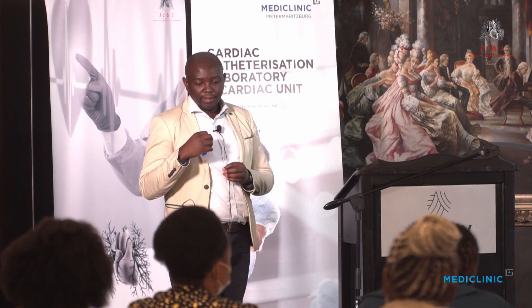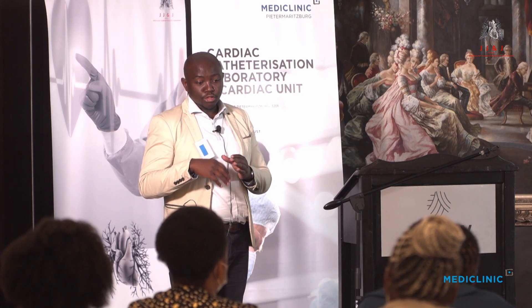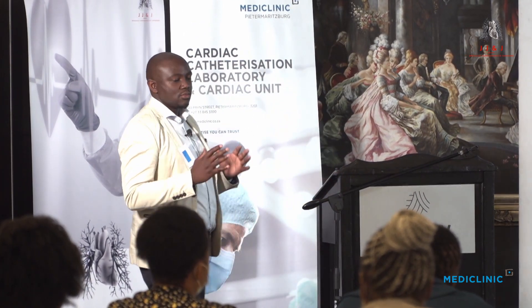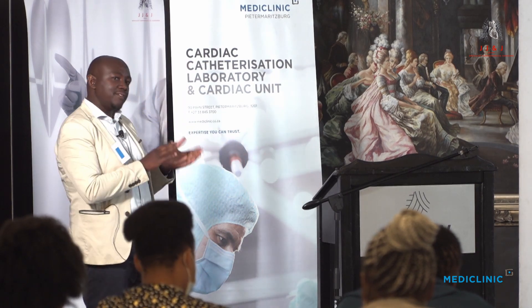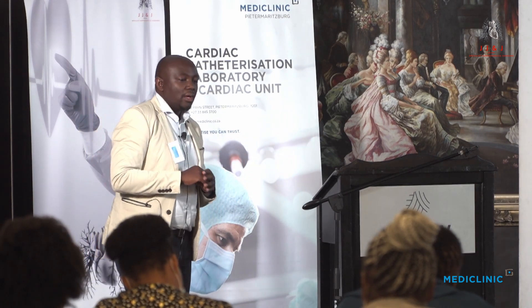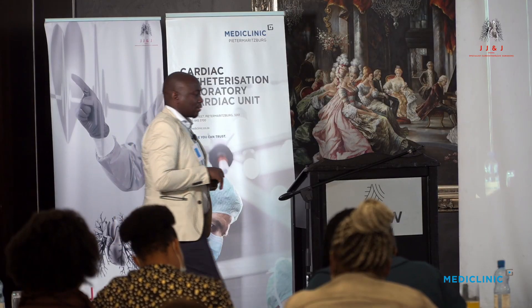I'll start in chronological order. For the bigger bubbles, which are the most damaging, you immediately want to call the coordinator, the perfusionist, and surgeons as quickly as you can. The smaller ones, which cause the machine to alarm, are really not that serious. Depending on whether you're doing a VV or VA — on VA we tend to cringe a lot, but for VV we don't get as worried.